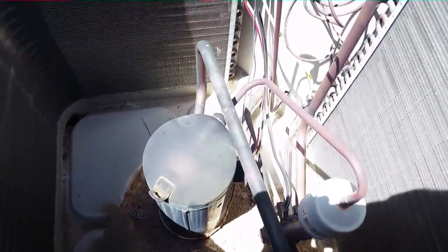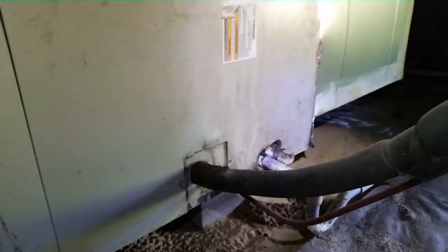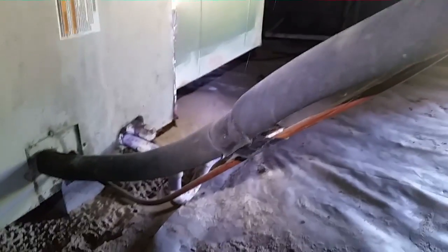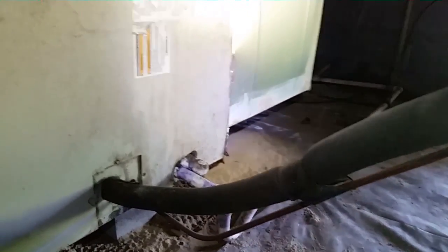We're going to take that out. We're also going to replace the evaporator on the inside because it is leaking as well. Here's our Nordyne air handler — Westinghouse is fancy for Nordyne, or Nortek or whatever it's called now. If you can see, our drain goes down, down and up. Maybe we can fix that — see if we have enough fall. Looks like it might not.